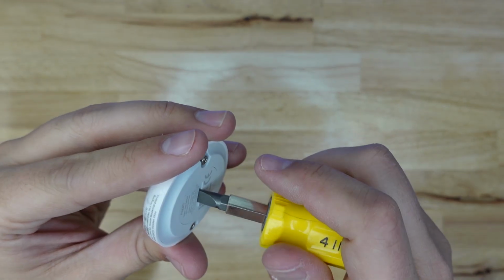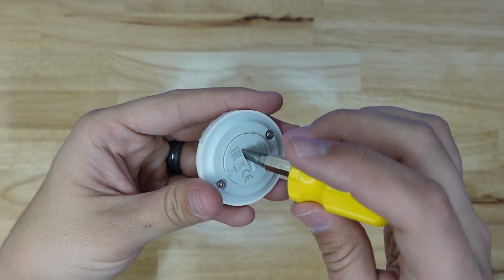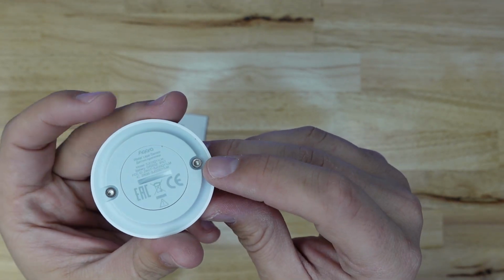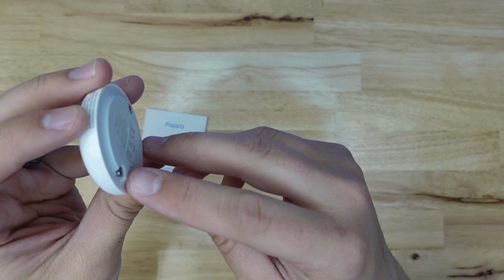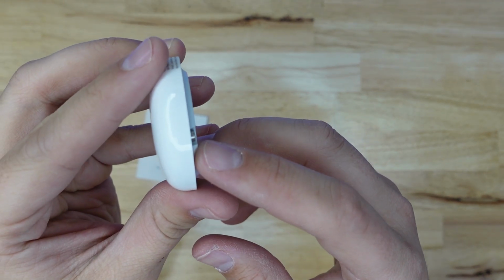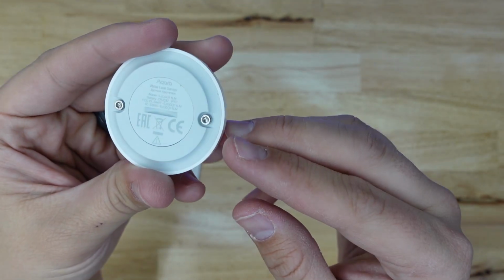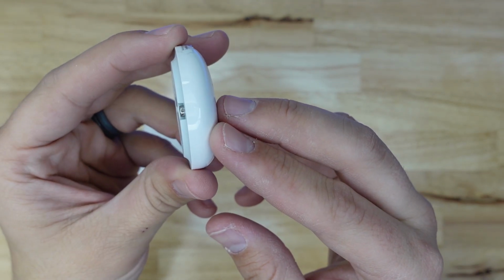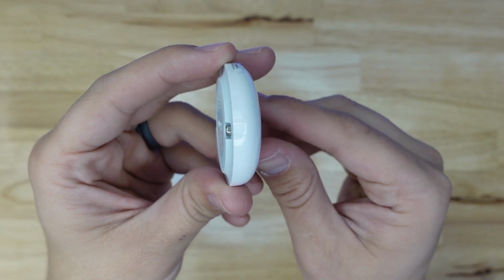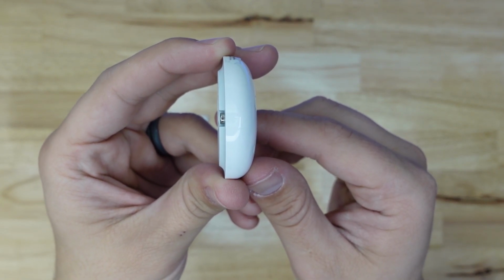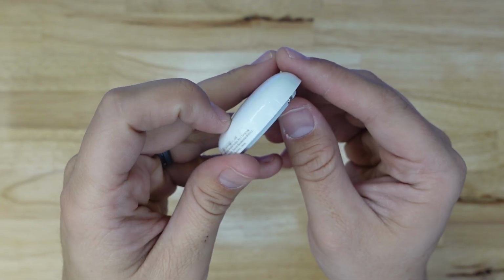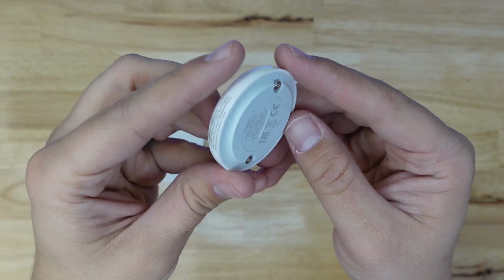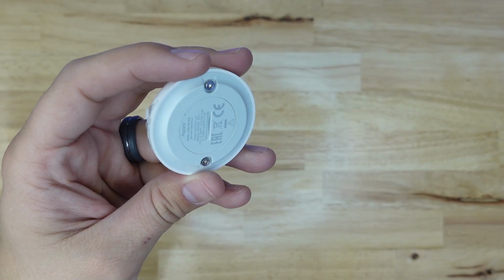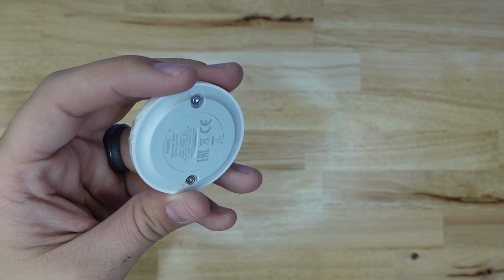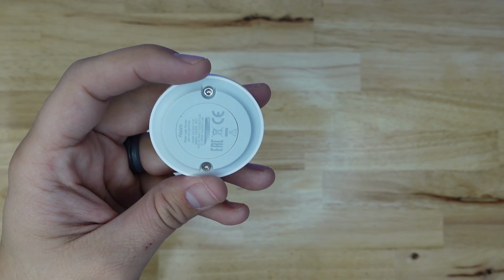On the back side, it has a battery compartment that can be opened with a flat head and two hex screws. The two screw heads are actually the electrodes that are used for sensing water. You can see that they're sunken into the flat surface at the bottom of the sensor by a few thousandths of an inch, and this makes it so that the sensor can sit on a flat metal surface without closing the circuit. It also means that it requires a very small amount of water to be surrounding the sensor high enough so that it touches those two screw heads.